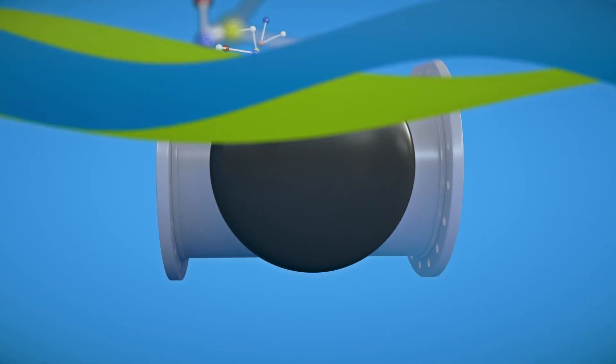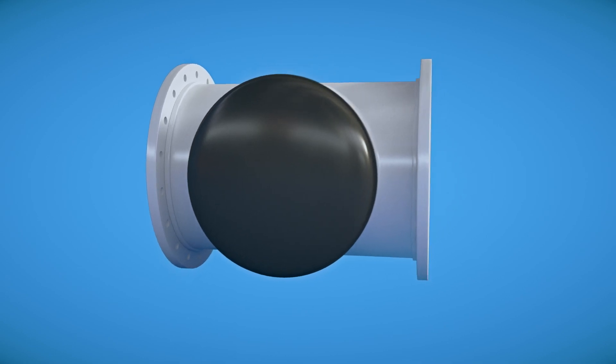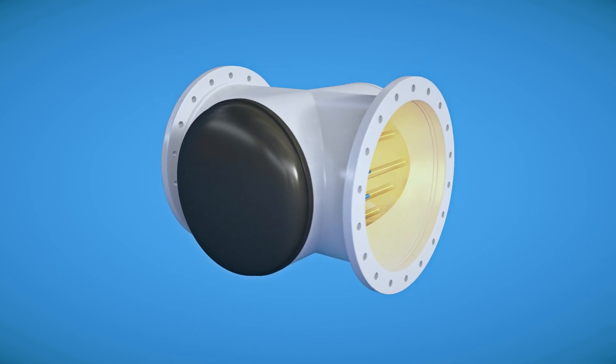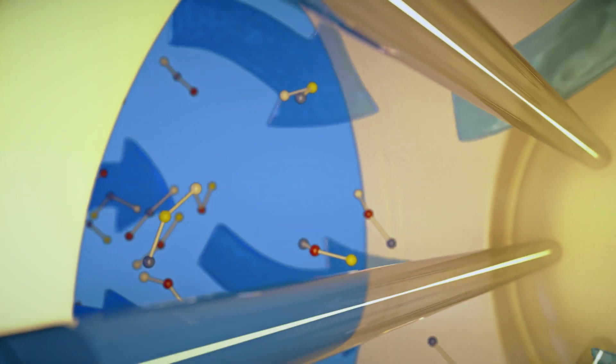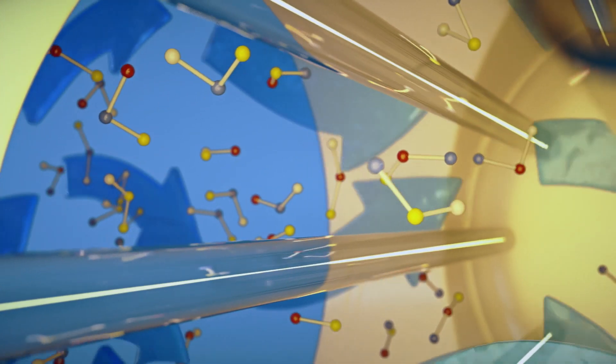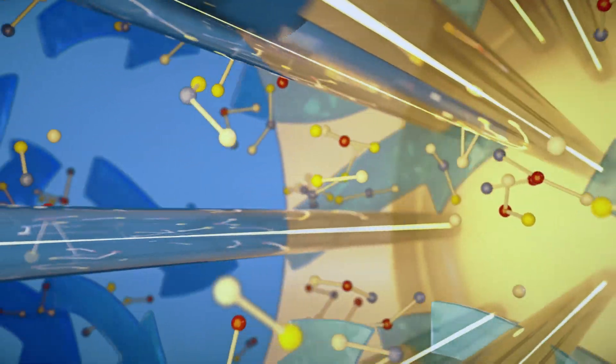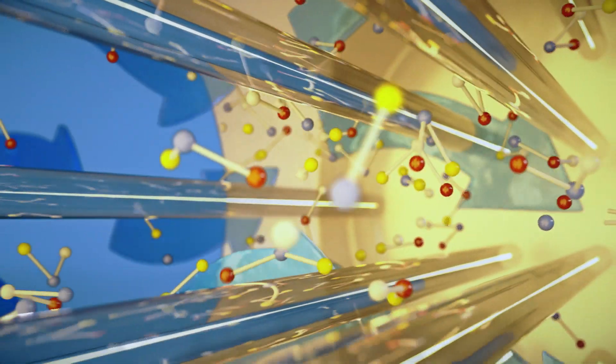Our system is composed of one large inline vessel that includes 18 specialized lamps that generate intense UV light. Water is passed through the vessel and around the lamps, exposing the water to the photolysis process and destroying any compounds that made their way through the previous processes.